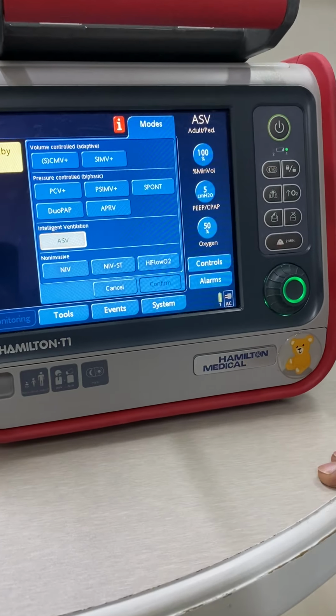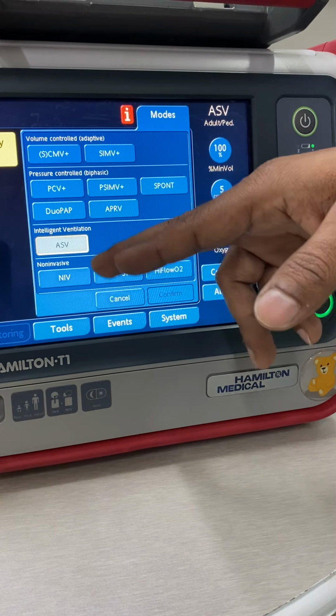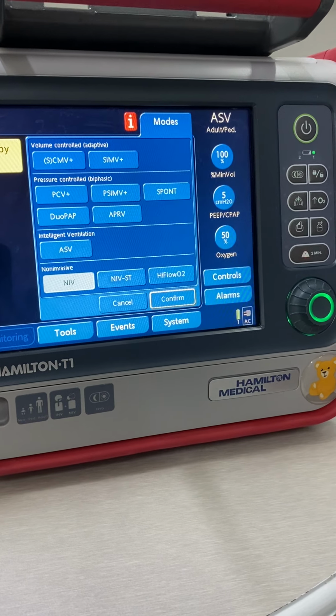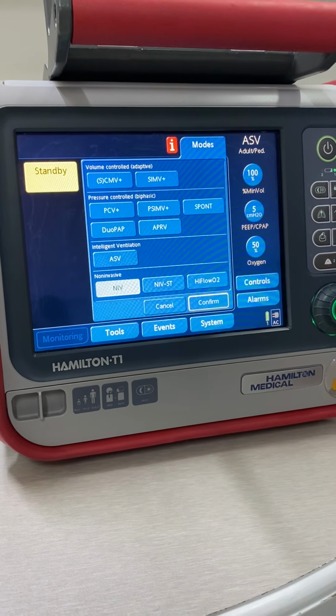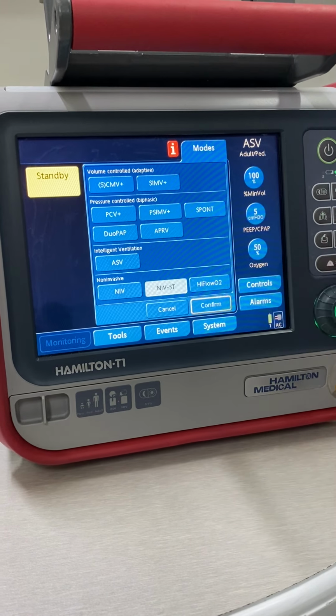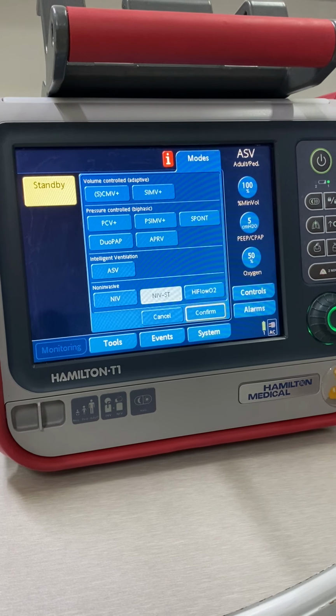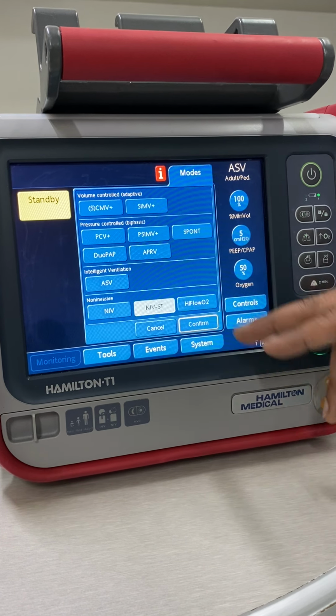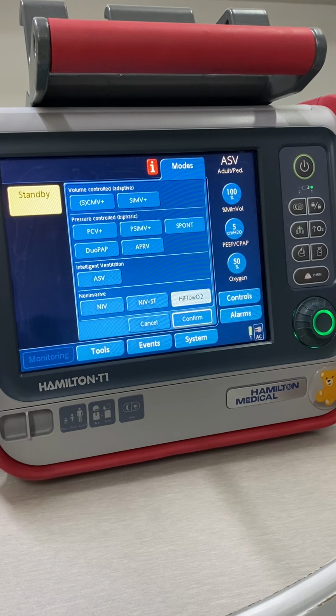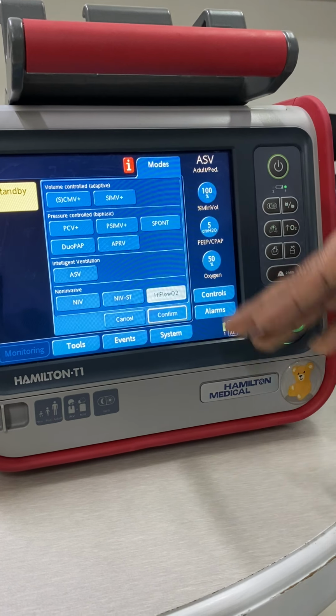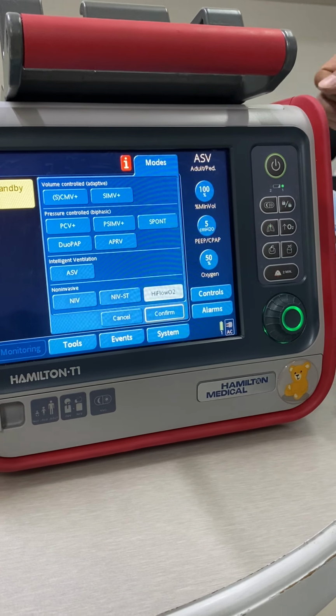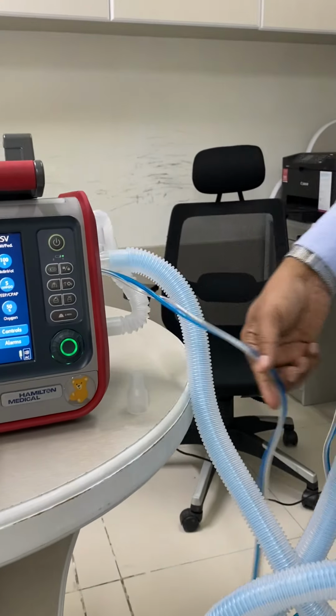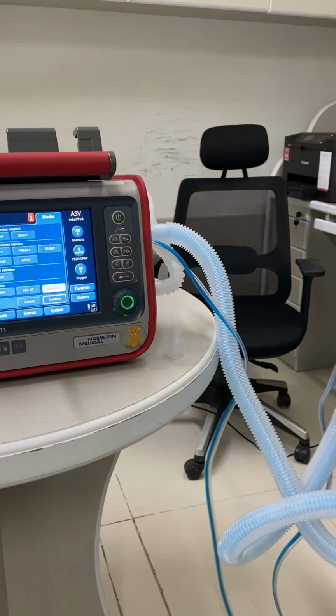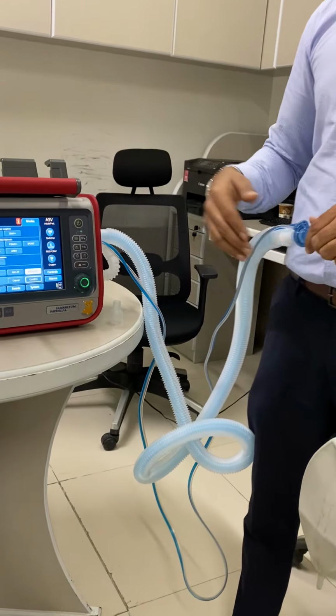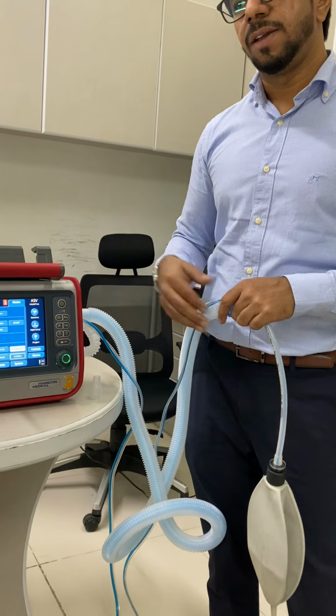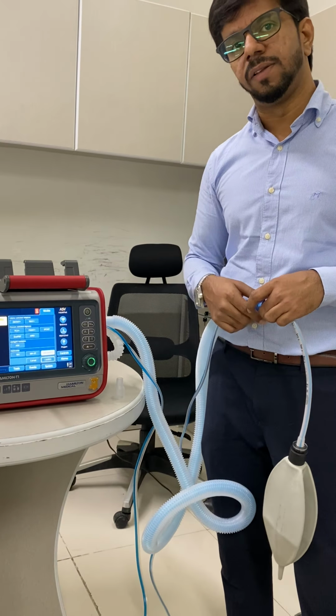We will explain about the modes in detail later on. Then we have also non-invasive modes. You can use NIV, which is the CPAP with the pressure support. NIV-ST is non-invasive spontaneous timed, which is the bi-level one. And also you have the high flow oxygen therapy as an option. For the high flow oxygen, you can use the humidified circuit without the flow sensor, with the high flow oxygen cannula, and it will go up to 80 liters per minute. And for the neonatal, it will go up to 12 liters.